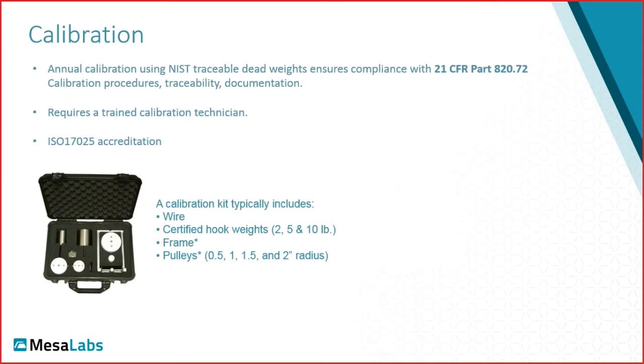Calibration is another important aspect to ensure accuracy, whether it's manual or automated testing. And typically, the FDA recommends, or it's an industry standard, that users calibrate their measuring devices annually. Our torque tester basically uses a strain gauge. It's very similar to a weight scale. So if you have a policy for the calibration of the weight scale, then the same would apply to the torque testing device. The regulation governing the calibration of these devices is in 21 CFR Part 820.72. If you want to look at it, they don't really require or tell you how often the testers need to be calibrated. They just want to make sure that you have a documented and repeatable way of calibrating the device, and you calibrate it regularly.